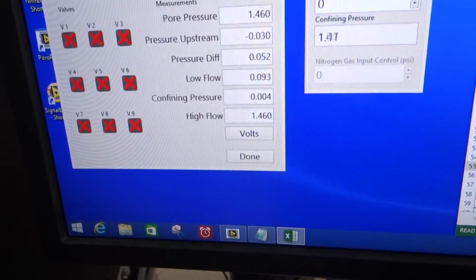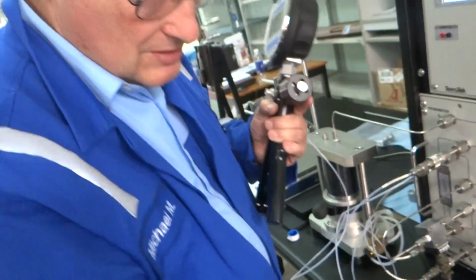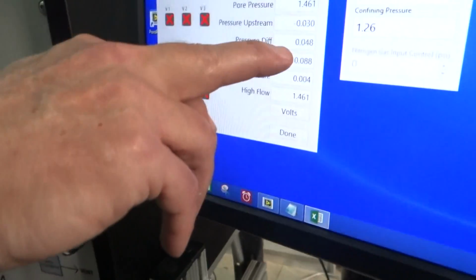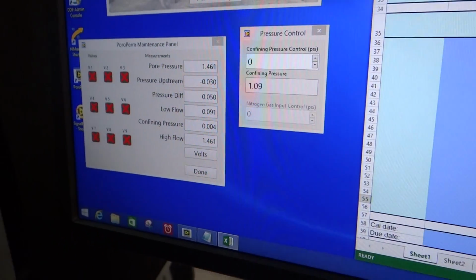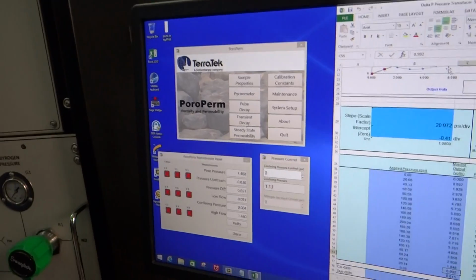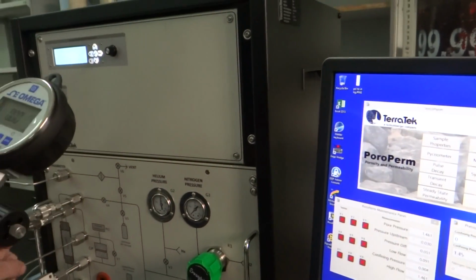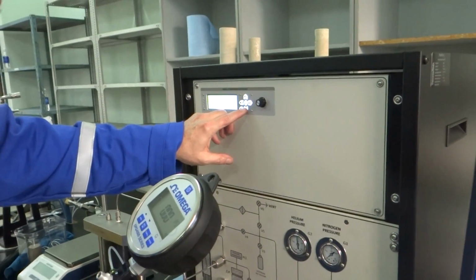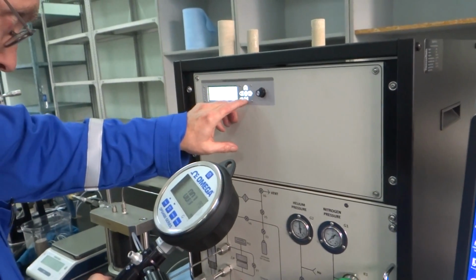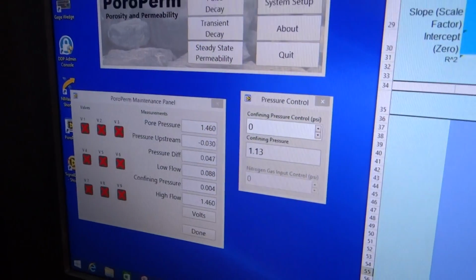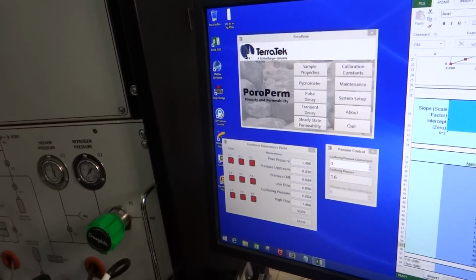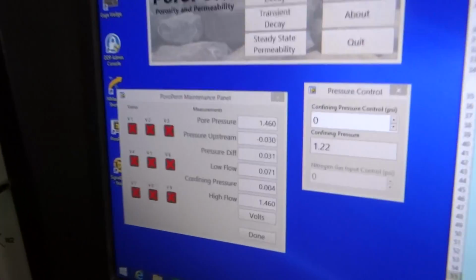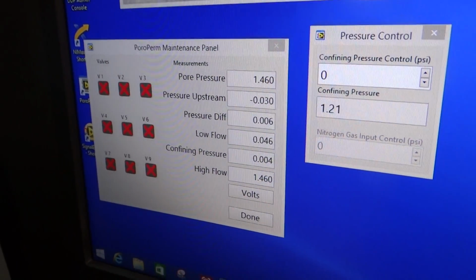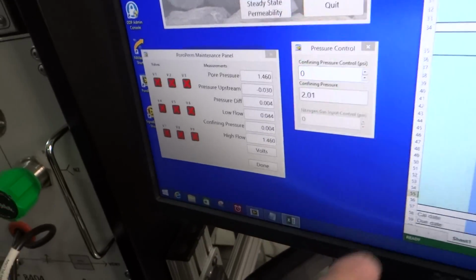So then to do the actual calibration, you'll do 10 points up and down. So you monitor the voltage here. If you want that right at pressure 0. Okay. So that would be your first point.